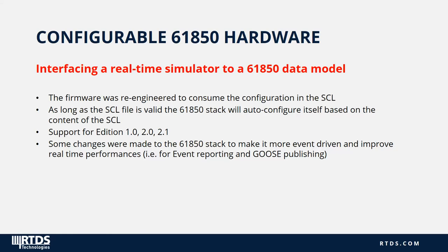Interfacing a real-time simulator to a 61850 data model. The firmware was re-engineered to consume the configuration within the SCL file. As long as the SCL file is valid, the 61850 stack will auto-configure itself based on the content, with support for edition 1, edition 2, and 2.1. There were some changes made to the 61850 stack to make it more event-driven and improve real-time performance.